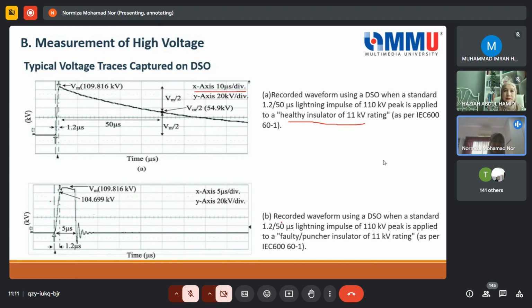And this is also the response obtained with the divider, but this one is faulty. So you can see that when there is a fault, there is a sudden drop in voltage, or voltage collapse, we call it. The voltage collapses to 0. That's an indication that the insulator failed.